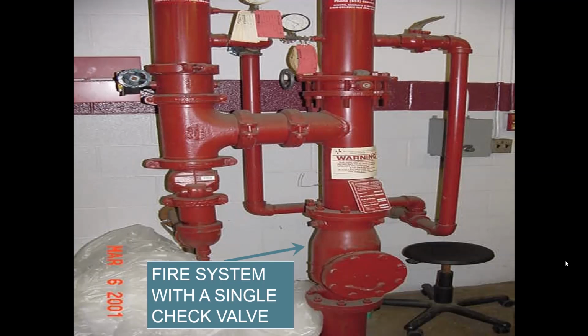When that time comes about, this should be either a double check valve or an RPZ that gets installed in its place. What you need to double check is to make sure, with that new backflow preventer going in, hydraulically, is that still going to be functional with the fire suppression system? If you have too much of a pressure drop or pressure loss with the new backflow preventer going in, the fire suppression system might not work as intended.